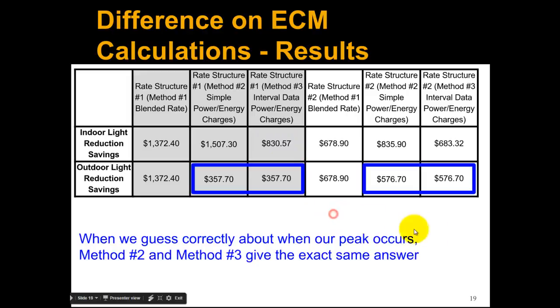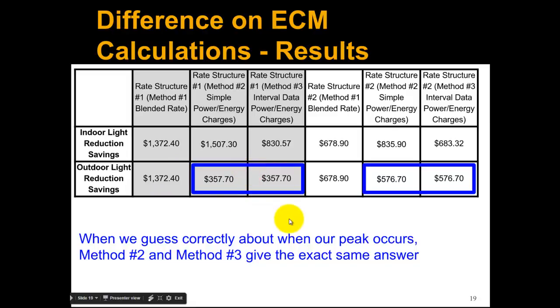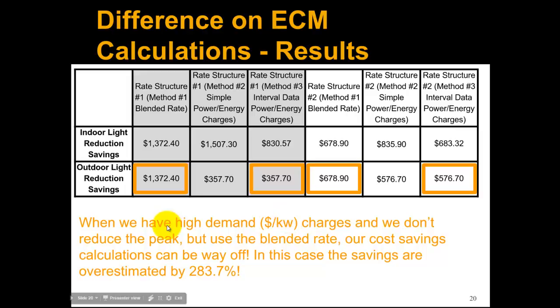Let's look at some other observations. These two numbers are exactly the same and these two numbers are exactly the same. For the outdoor light reduction, we guessed that we didn't get any peak reduction, and we didn't — so when we guess correctly about when our peak occurs, method two and method three give the exact same answer. However, if we use the blended rate and we didn't reduce the peak, as in the case of the outdoor light, our cost savings calculations can be just ridiculously off. These two are actually 283% off. That's why you want to be really careful and never use the blended rate.